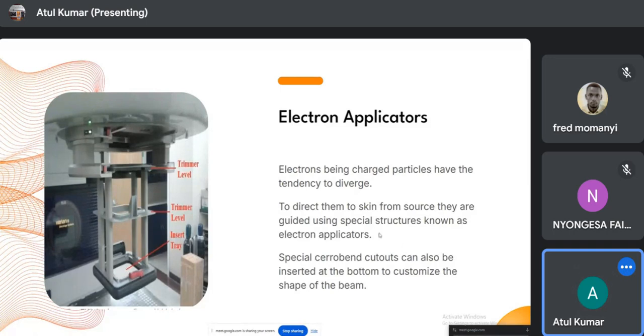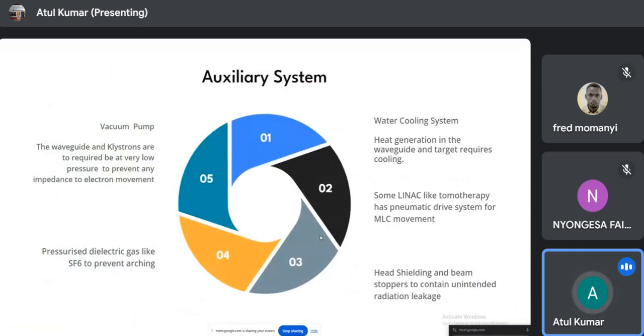There are several other systems also. Obviously, you need cooling, you need a vacuum pump, because the entire process of the waveguide and klystron and magnetron, everything needs vacuum. Like you have seen in the incandescent bulb that we have talked about, you have to encase it with glass and fill it with a non-reactive gas, because if oxygen or any other reactive material interacts with the electron, the electron will die, and obviously they will collide and other things. So everything should happen inside a vacuum system, and to have that vacuum, you have to have a vacuum pump. Some of the systems like klystrons and magnetrons run on a very high voltage. So with those high voltages, obviously there are chances for sparks, like the lightning effect that we see. So to prevent that, you have to have a very good insulator gas. SF6 is used as an insulating gas.